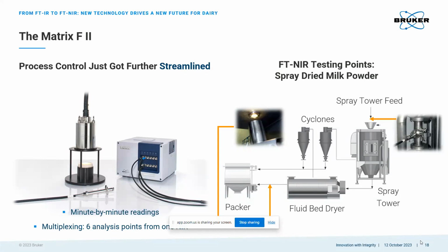This online powder analysis directly impacts the yield simply by analyzing moisture, along with additional parameters such as protein, fat, and lactose content. So in a situation where we normally turn to a production lab to run moisture analyses, which are, again, going to be run every few hours, we can now obtain moisture results every minute with an accuracy of 0.15%. So it's comparable to the Karl Fischer reference method. And with such monitoring, the moisture content can now be adjusted closer to our target value with even greater consistency. And not only do you see direct cost savings due to increased yield and reduced energy costs, but the risk for out-of-spec production is going to be greatly minimized.